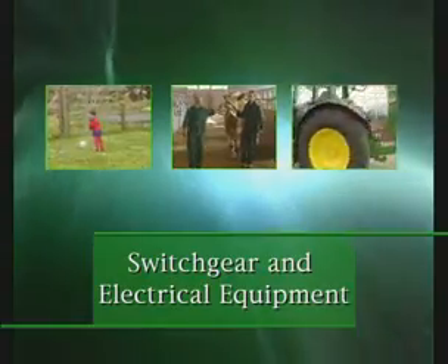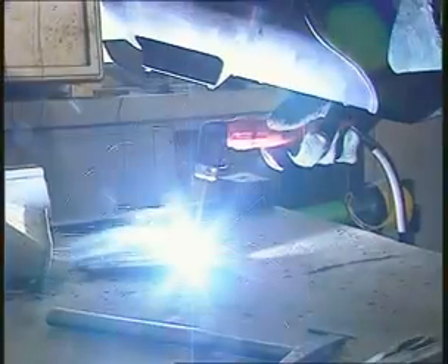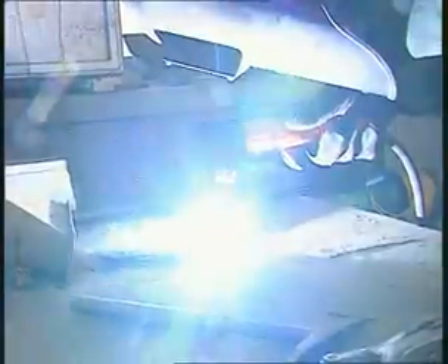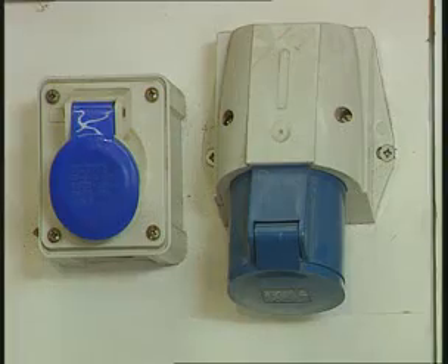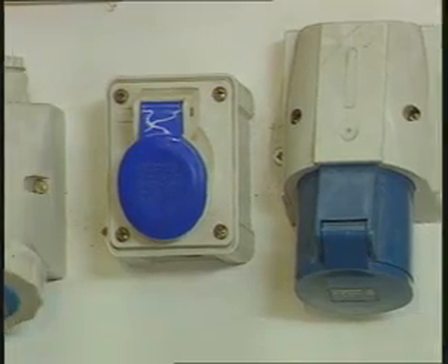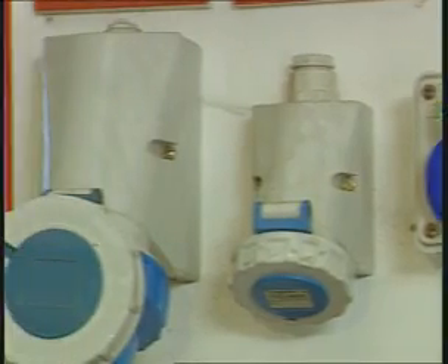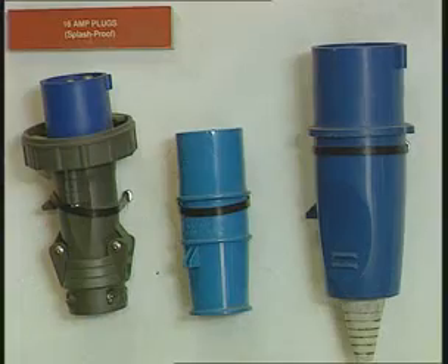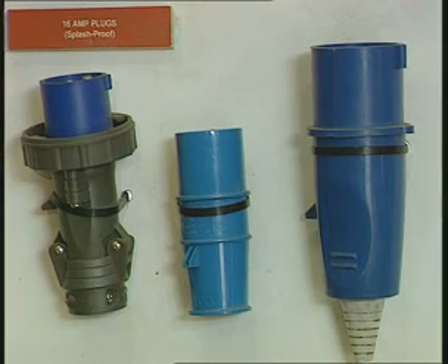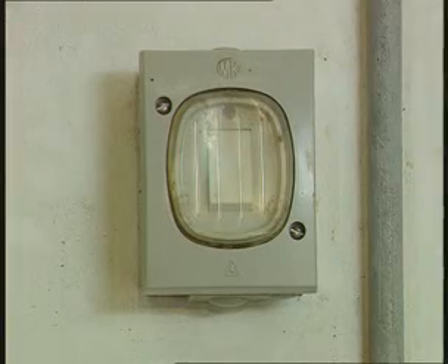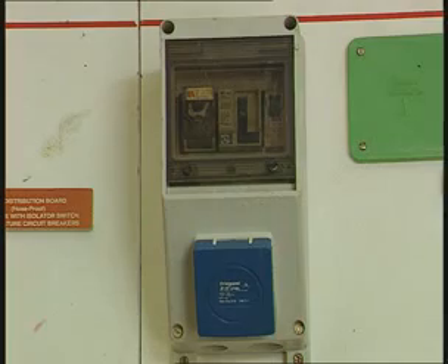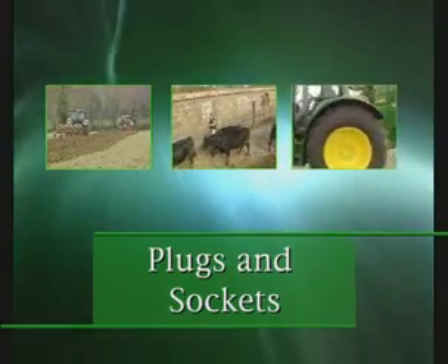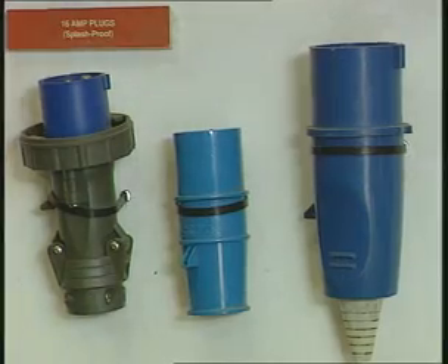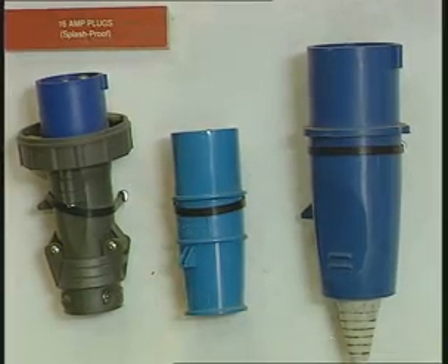Switchgear and electrical equipment. The national wiring rules frequently refer to IP ratings for electrical equipment and fittings. All switchgear, plugs and sockets used on farm buildings must be of an industrial type. They must offer a minimum IP44 degree of protection against the entry of foreign objects and moisture. Plugs and sockets. Two types and sizes will cover almost all uses on farms.